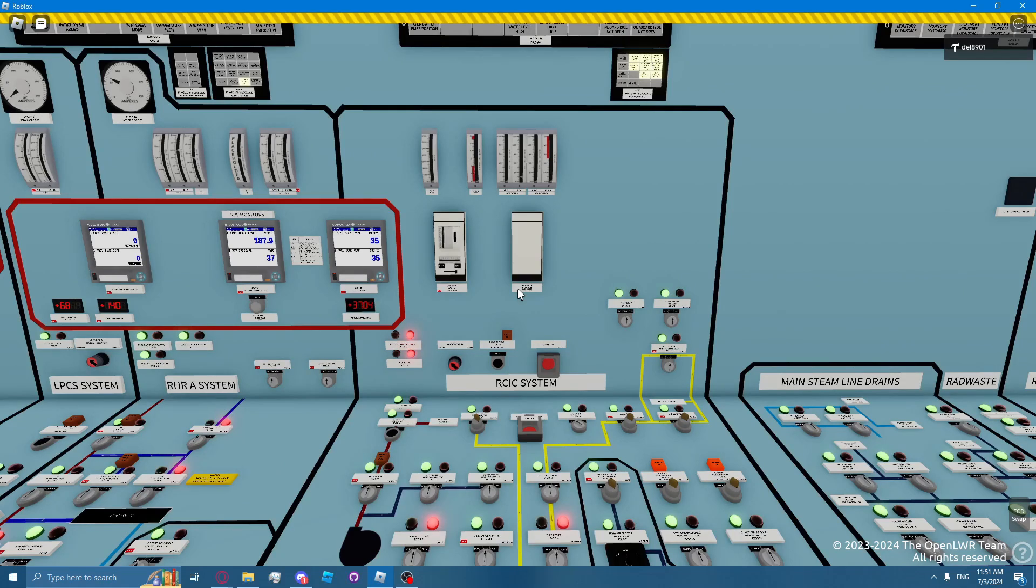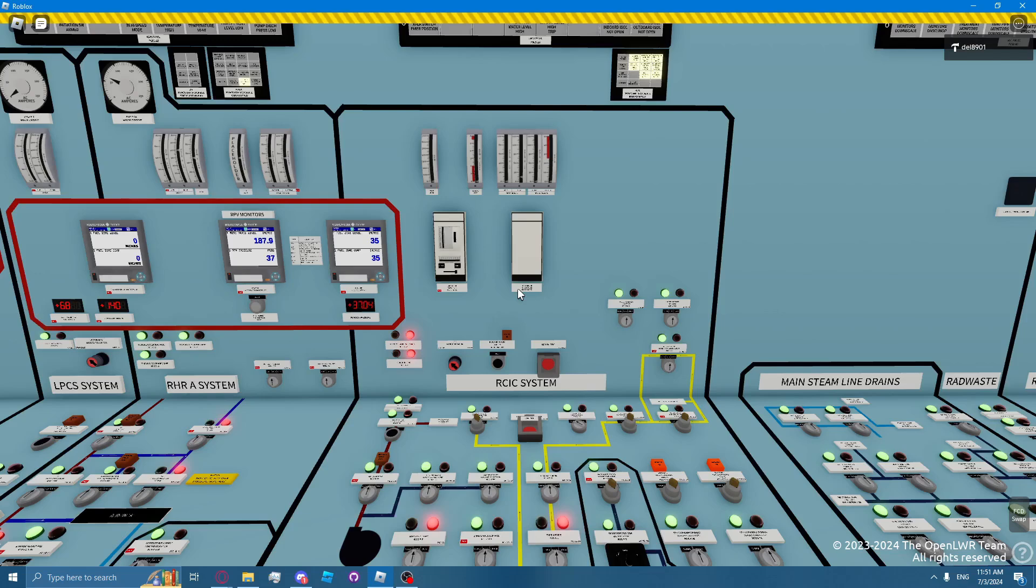The RCIC turbine is designed to accelerate from cold and standby to full load conditions within 30 seconds. The RCIC turbine is a non-condensing Terry turbine, designed to operate with steam supply pressure anywhere between 150 to 1135 PSIG.